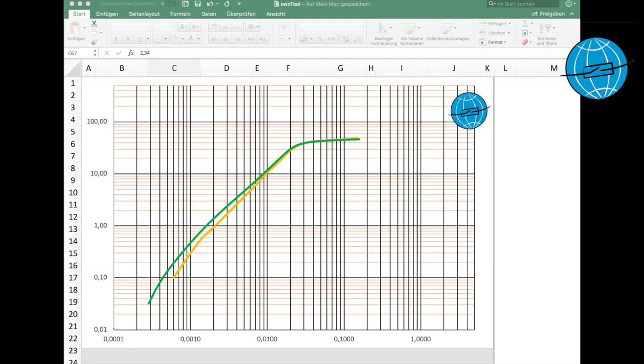As we can see our results are relatively close to each other and it gets really interesting if we measure the entire magnetization curve in this way. I've prepared this in advance. In green we see the original imported characteristic trendline of the CT analyzer and in yellow our own recorded characteristic. As we can see everything from 10 volts upwards is pretty much in line. It's just this upper part that we need to estimate the knee point voltage.